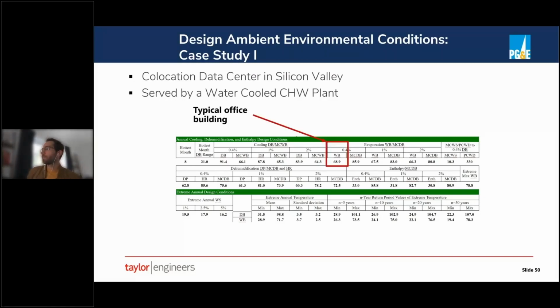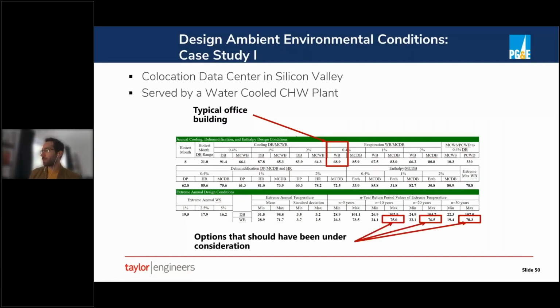So a typical office building, the cooling towers in this climate would have been selected for an ambient wet bulb of 68.9 degrees Fahrenheit. What the engineer on this project elected to do, however, was use 67.5, which is even more aggressive than what you would likely use for an office building. So that was a bit of a head scratcher.